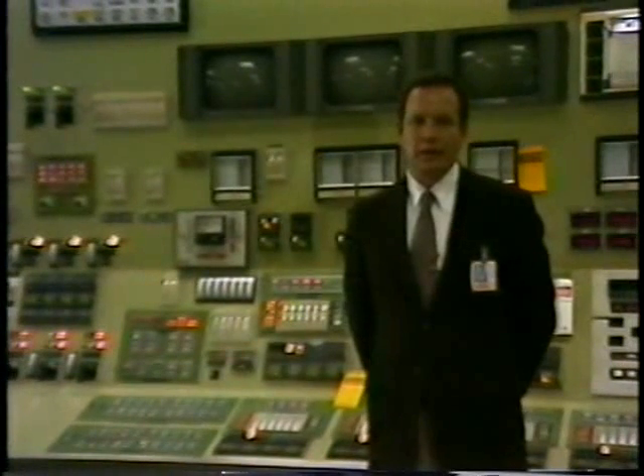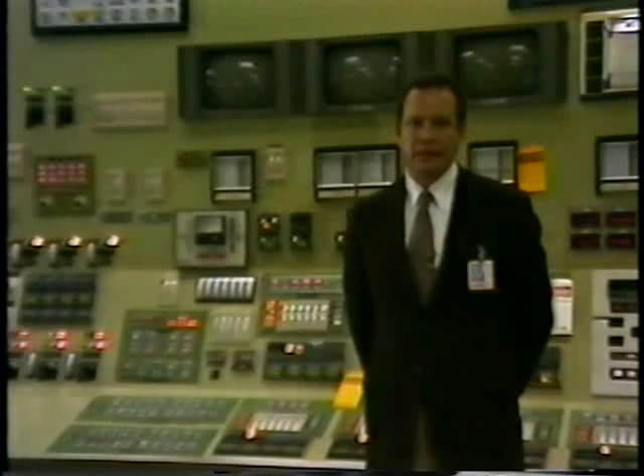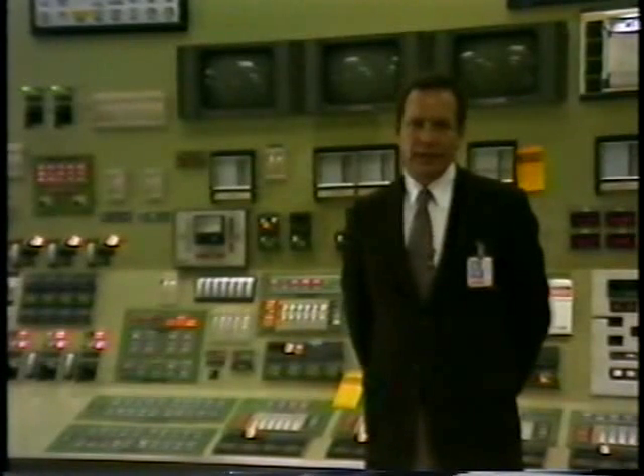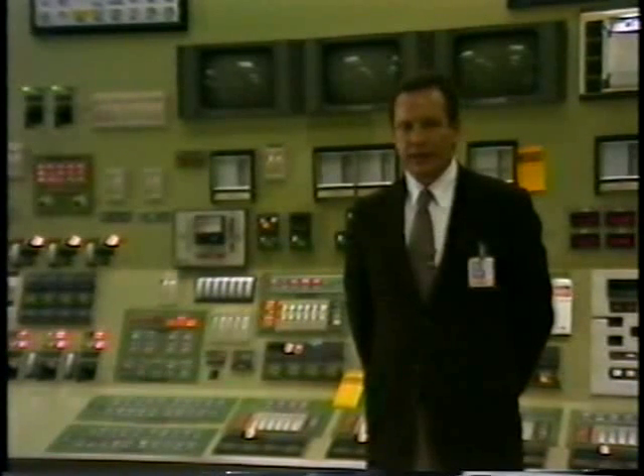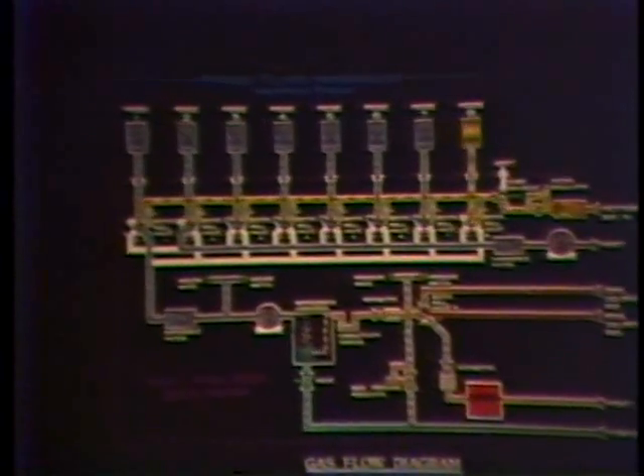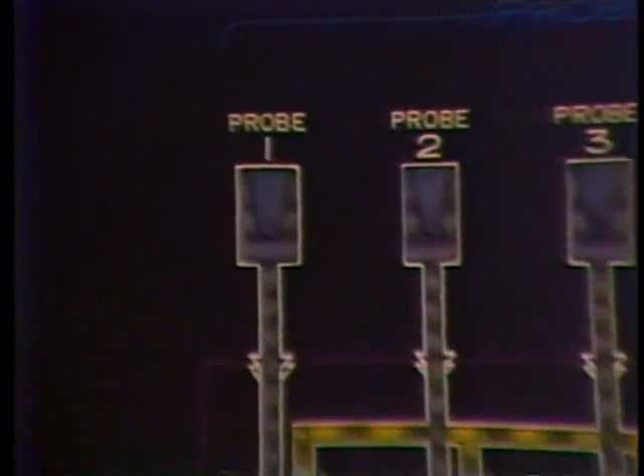The KVB Coal Fire Protection System is a fully automatic, self-calibrating system designed to protect against fires or explosions in coal pulverizing equipment. The computer-controlled sample acquisition, conditioning, and analysis system contains all the improvements and refinements dictated by research and experience spanning 3 decades at hundreds of locations, successfully overcoming the special problems presented by gas sampling in pulverized coal systems. The system's instruments and sample handling components have demonstrated reliable, precise performance.